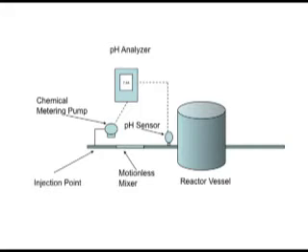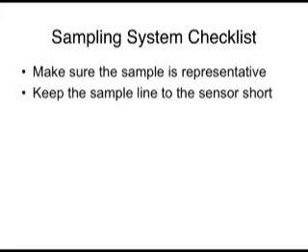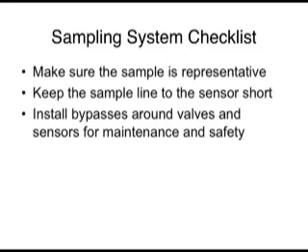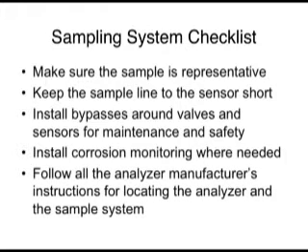When you're designing an inline or atline analyzer station, you need to spend most of your time getting the sampling system right. So here's a basic checklist to work from: make sure the sample is representative; keep the sample line to the sensor short; install bypasses around valves and sensors; install corrosion monitoring where needed; and follow all the analyzer manufacturer's instructions for locating the analyzer and the sample system.